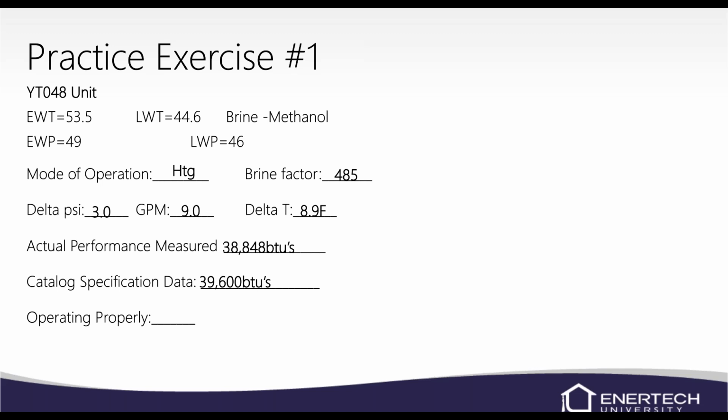So as long as we're within 10% of 39,600, which that would be about 35,600 BTUs, somewhere right around there, on the low end. So we're above that 36,000 BTUs minimum. So we are within 10%. So yes, the unit is operating properly.